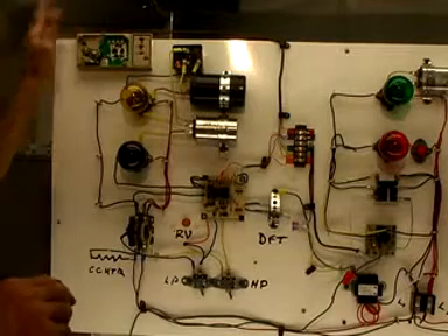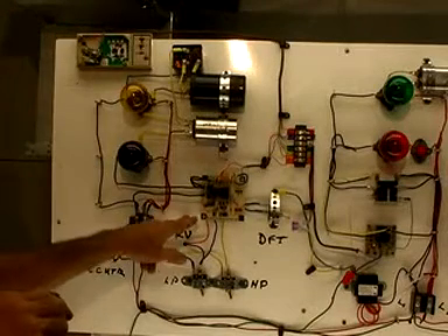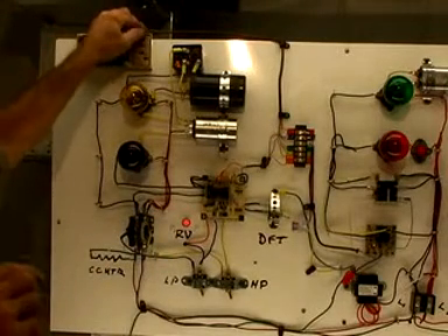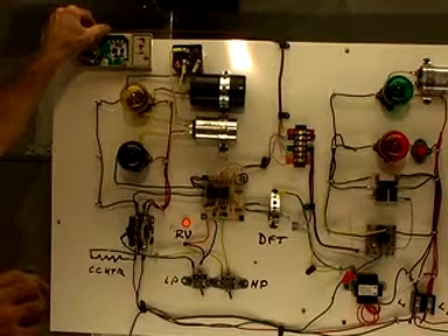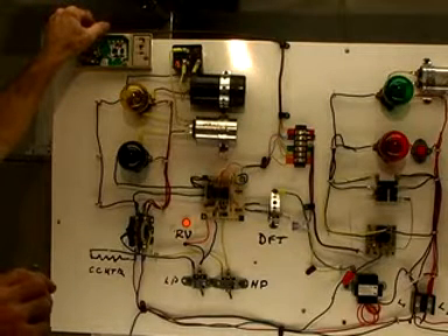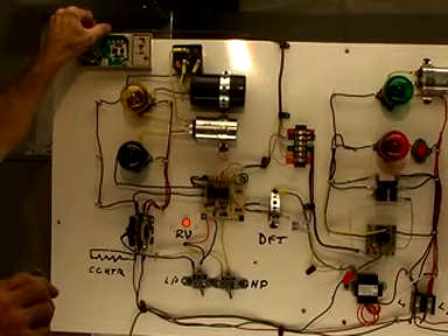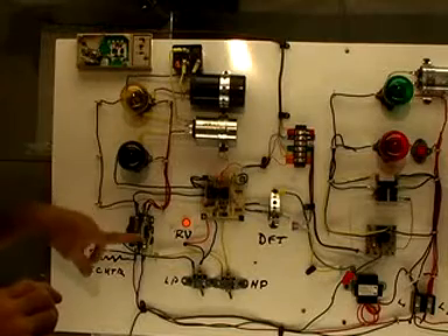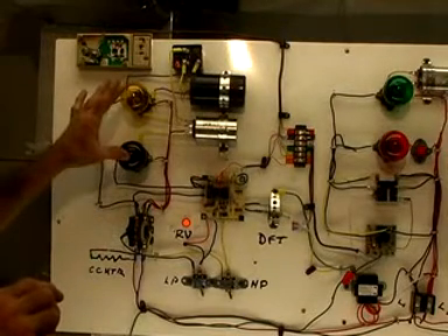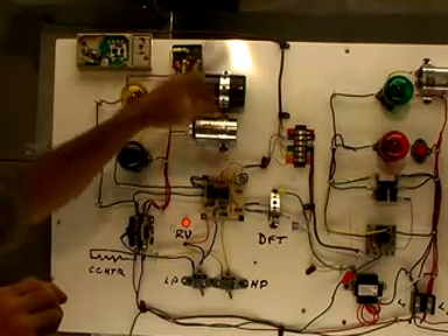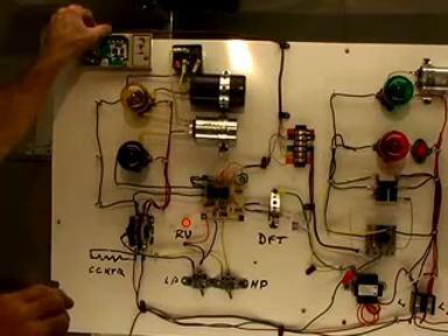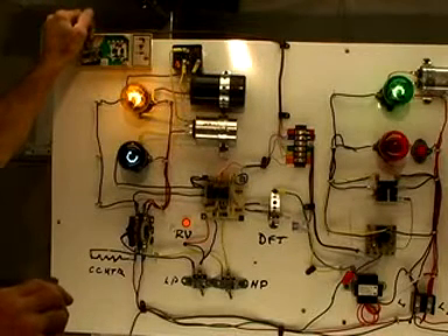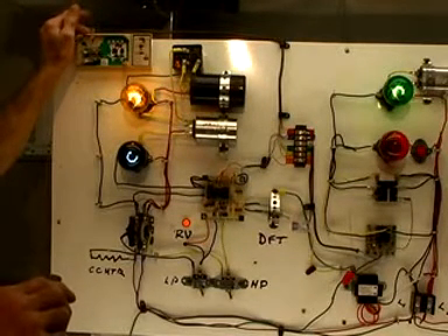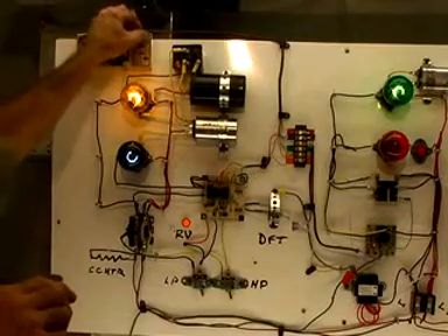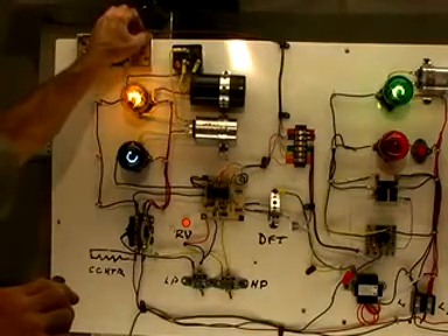So when I actually set the thermostat to cool, the only thing you're going to see is the reversing valve light up. Now if we back down on our set point to where it'll call for cool, then the contactor is going to pull in and our condenser and compressor lights come on. Of course our blower motor will come on again. So let me do that. Now the system's running in cool. Okay, let's go back off, and I'll pause the camera while the lights change, and we'll come back running heat.